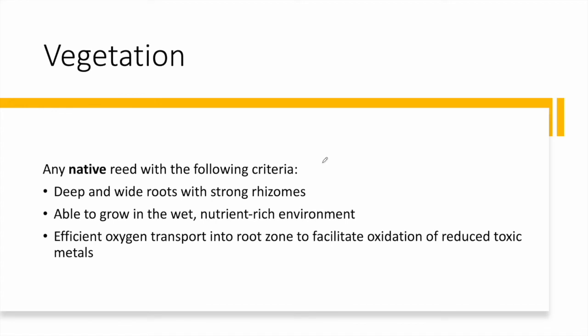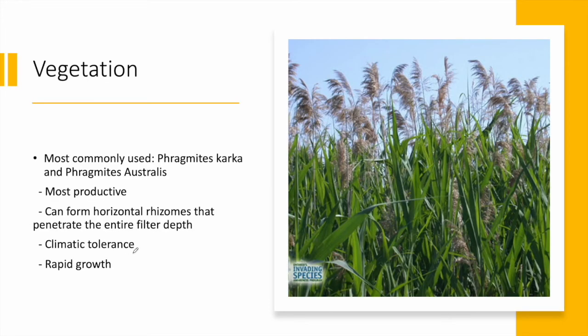For vegetation, choose a native reed with deep wide roots and strong rhizomes, capable of growing in wet nutrient-rich environments and transporting oxygen into the root zone. The most commonly used species are Phragmites karka and Phragmites australis, as they are the most productive, form horizontal rhizomes penetrating the entire filter depth, have high climatic tolerance, and a rapid growth rate.